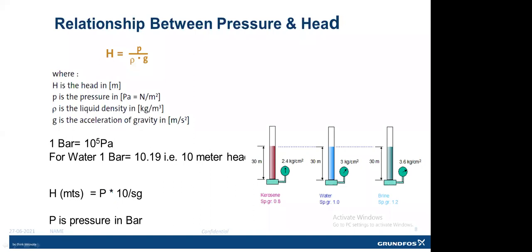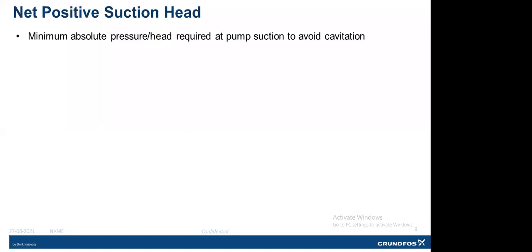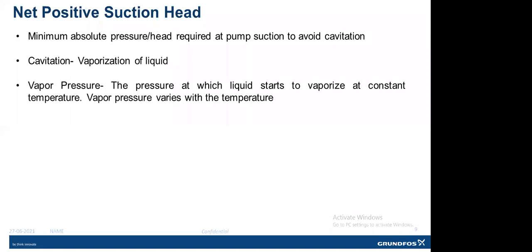Another terminology related to pump operation is net positive suction head. What is net positive suction head? It's nothing but the minimum absolute pressure or head required at pump suction to avoid cavitation. And cavitation occurs due to vaporization of liquids, and vaporization occurs if the absolute pressure is lower than the vapor pressure of the liquid; it starts to vaporize.